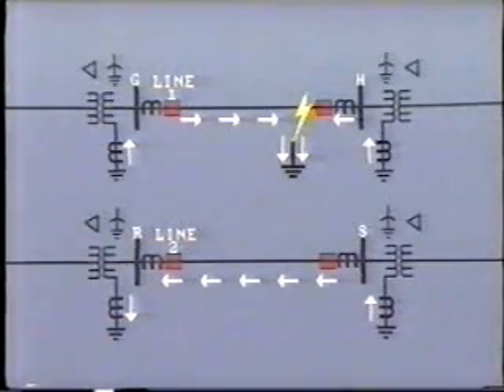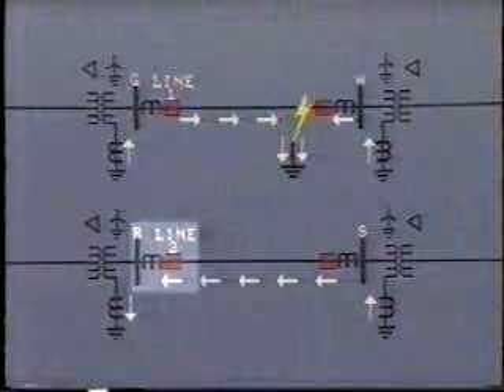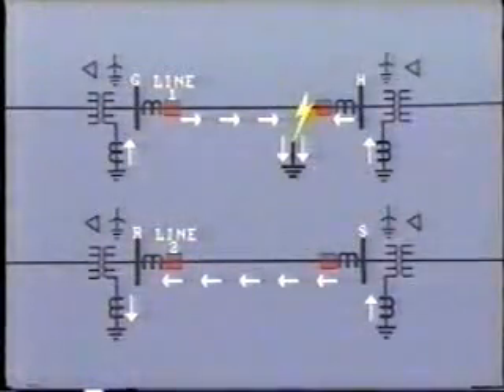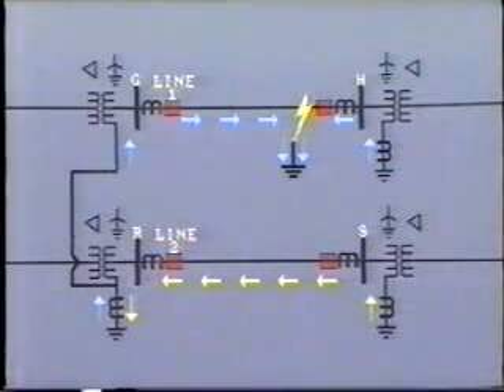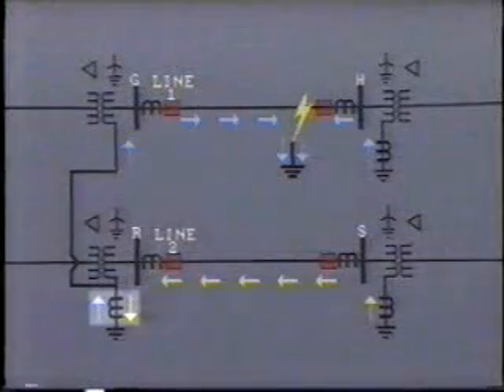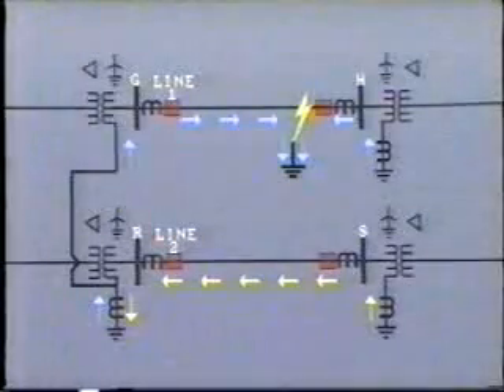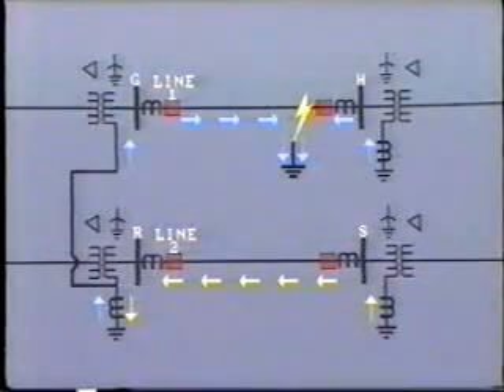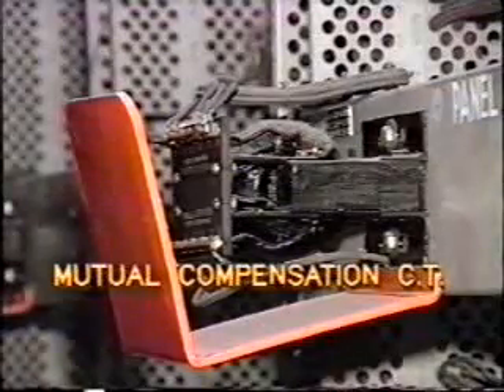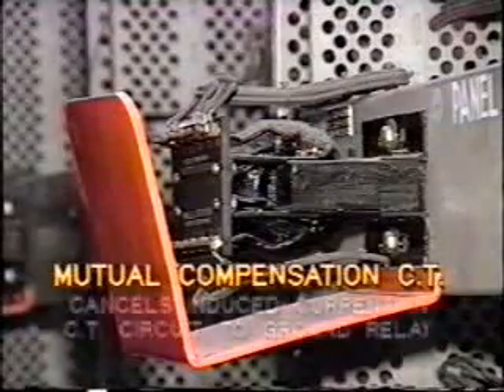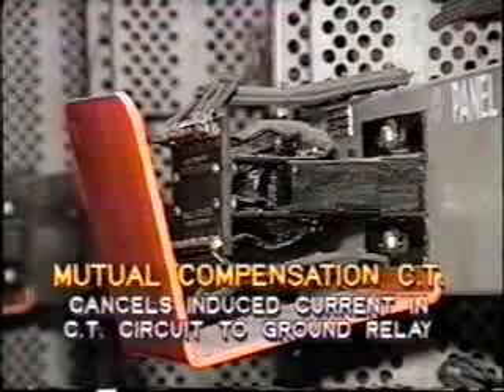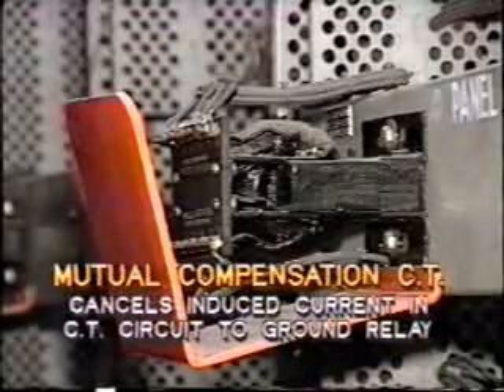In this particular scheme that we're studying, another method of preventing breaker R from opening would be by paralleling the neutrals of the transformers at R and G to a common ground connection, if they are close enough together. The current passing up the neutral would be greater than the induced current passing down the neutral, and therefore polarization of the directional relay at bus R would be correct. Another solution is to use mutual compensation CTs, which remove, that is, cancel the induced current in the CT secondary circuit to the ground relays.